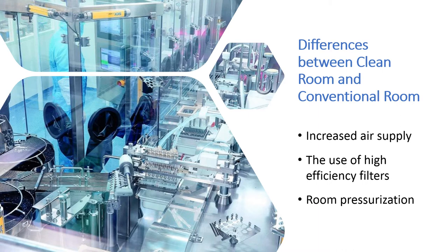A clean room would have at least 10 air changes per hour and could be as high as 600 for absolute cleanliness. The large air supply is mainly provided to eliminate the settling of the particulate and dilute contamination produced in the room to an acceptable concentration level.